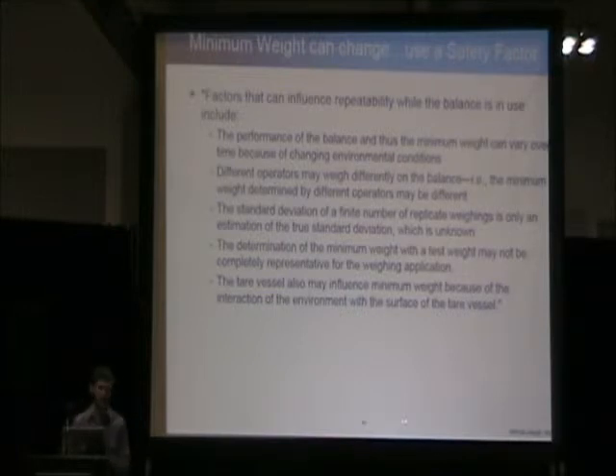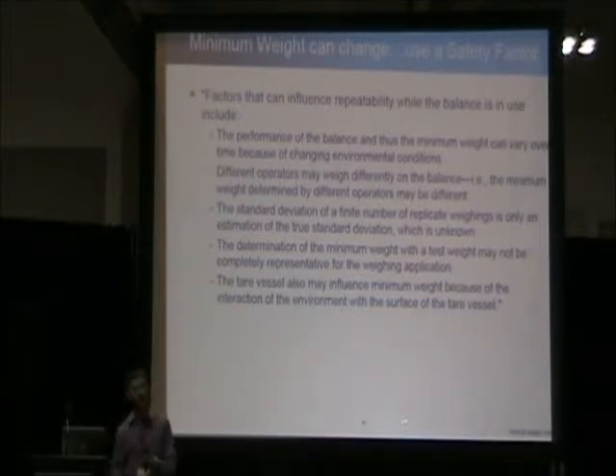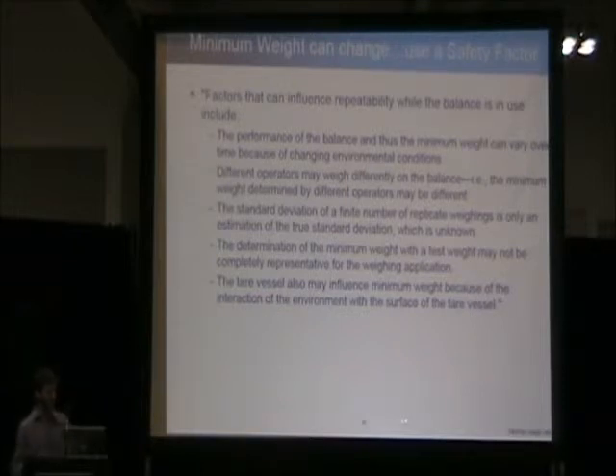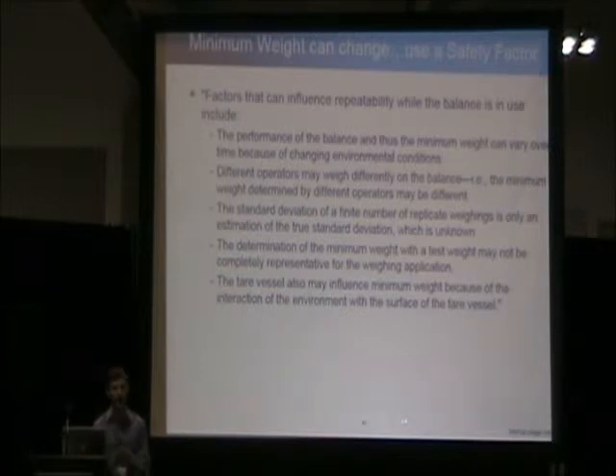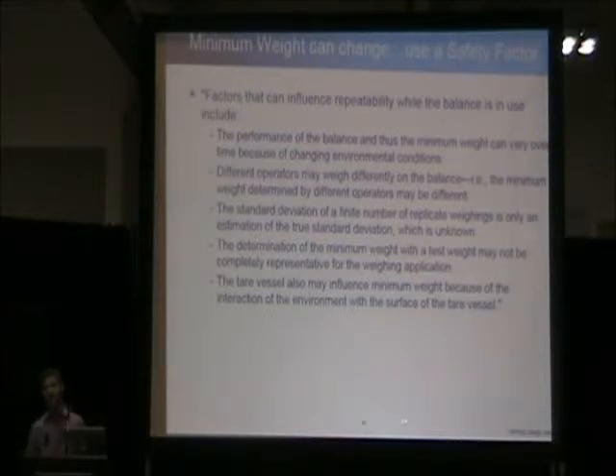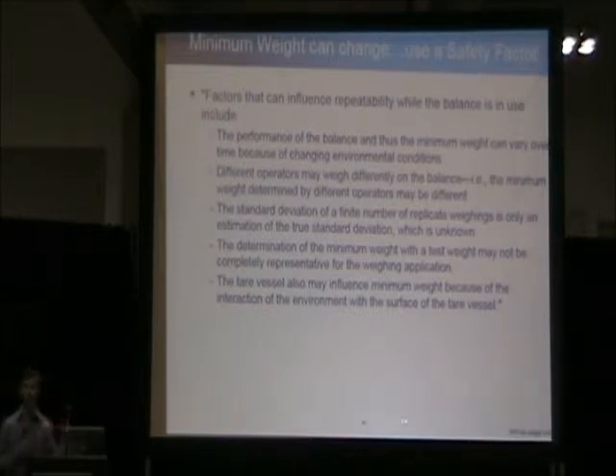Let's say technician 1 comes in and weighs on an analytical balance, but is placing their hand inside the draft shield, which is bringing in heat from their hand, electrostatics from their glove, and also airflow. And then you have technician 2 that is not doing that, that's using a forceps or a spatula to bring their sample in without actually bringing their hand. That very simple change of having your hand placed in the balance and having the other technician not having their hand in the balance is actually going to cause the uncertainty of measurement to vary between those two different technicians.